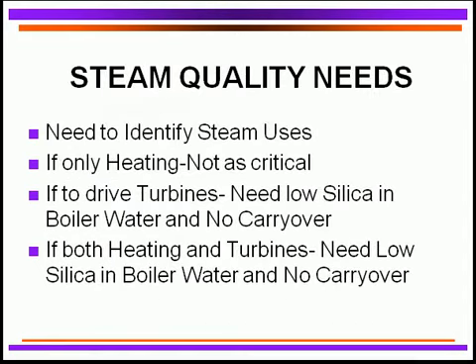What do we need to do with the steam? First, we need to identify the steam quality required for boiler operation. Is it for heating only, or is it for driving turbines? If it's for heating only, we're not as critical on steam quality. But if it's driving turbines, we need low silica in the boiler water and no carryover to protect the turbines. If both uses are happening simultaneously, or if it's critical process equipment, we must do a much better job of ensuring good quality steam.